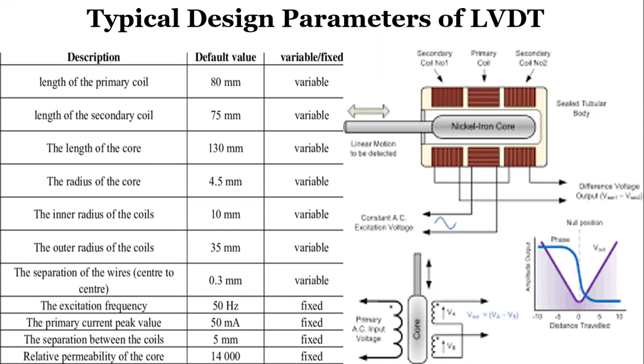Then you have some fixed parameters: the excitation frequency of 50 Hz is fixed, the primary current peak value is 50 milliamps, the separation between the coils is 5 mm, and the relative permeability of the core is 14,000. So these are the fixed parameters, and these are all the typical parameters while we are considering the design of an LVDT. This is just an add-on. So that's all about the selection criteria and the significant parameters to be considered for the selection of a transducer. Hope you have enjoyed it. Thank you very much.